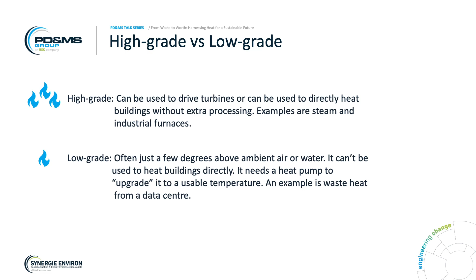High grade, ready to go. You might hear that interchanged and people talking about quality of heat - that's what it means. I put this one in because it can be a bit of a tripping point for people: what is a heat exchanger and what is a heat interface unit? I say it's like all squares are rectangles, but not all rectangles are squares. So all heat interface units will have a heat exchanger, but not all heat exchangers are heat interface units.